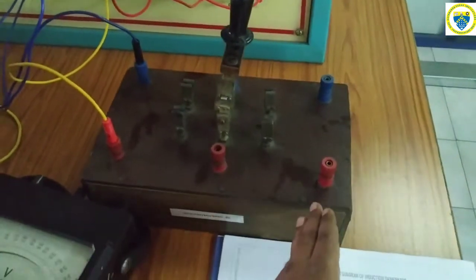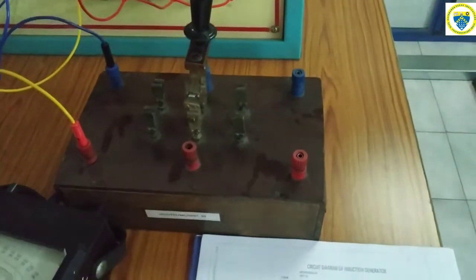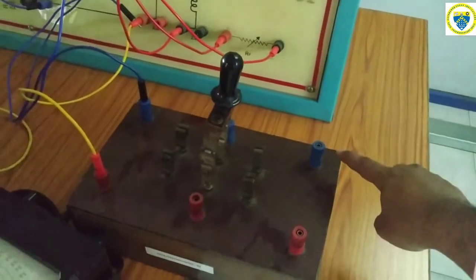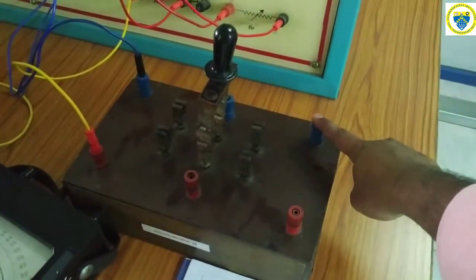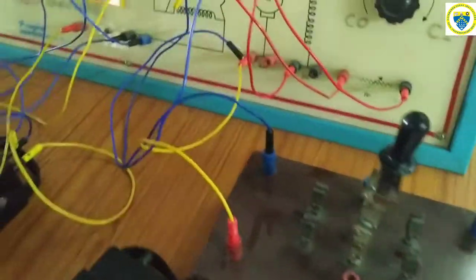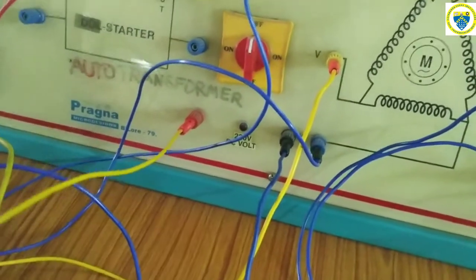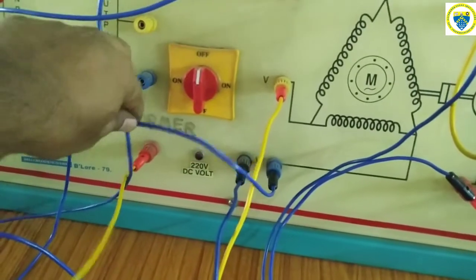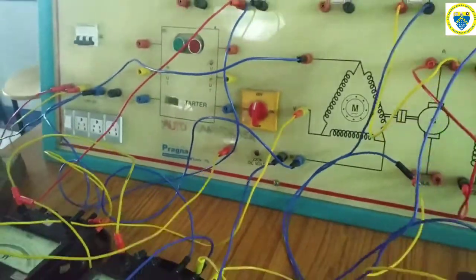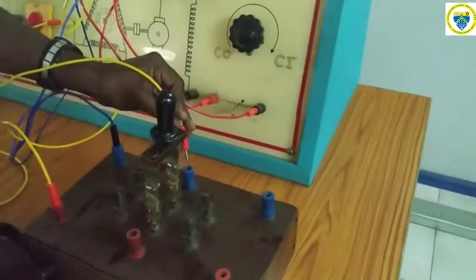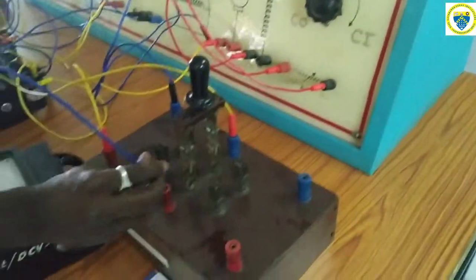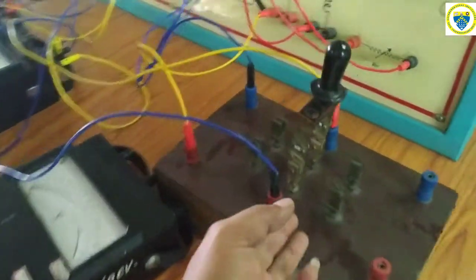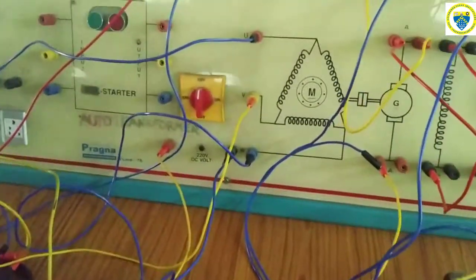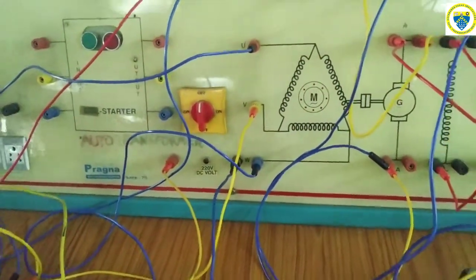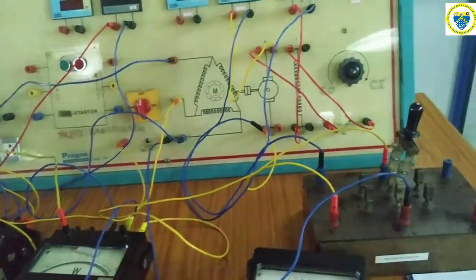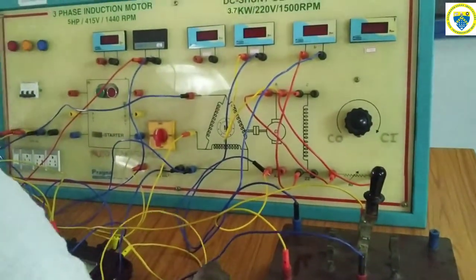Also at the right hand side of the DPST switch, we should connect an external DC supply of 220 volt. Here this should be connected to positive and this should be connected to negative. Here we will have terminals for connecting that 220 volt external DC supply, and this will be a positive terminal and it should be connected to the positive terminal of the DPST switch, and the one more terminal should go back to the negative end here. Okay, so this is the overall connections we have in case of an induction generator.